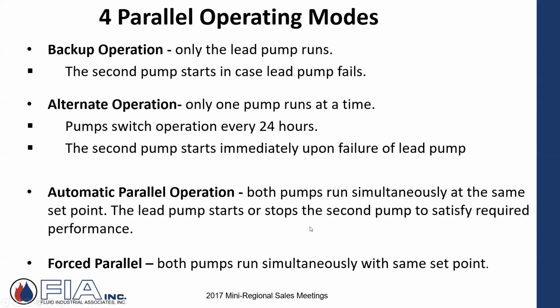One of them is just straight backup. One runs, one's backup. Something happens, the one that's supposed to be running fails, backup turns on. That's one mode. I could have alternate, which makes a hell of a lot more sense. And that says one runs, one's backup. But every 24 hours, you change who's the guy running, so I have equal runtime, equal wear.